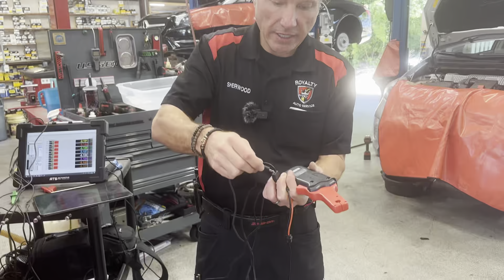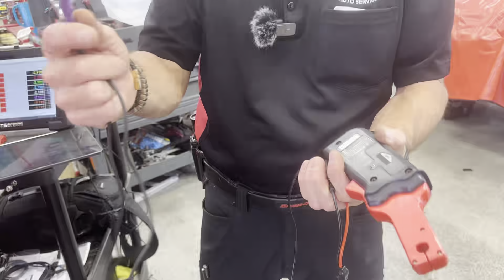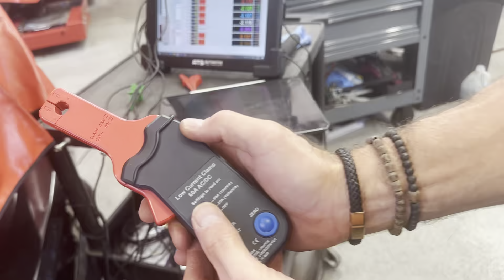amp clamp. So the amp clamp is going to come like that, okay? Go ahead and disconnect this, just how you did. These little black jumpers come in the kit, okay? You're going to take your lead, so I've got the purple lead. You're going to take the black jumper and close to the end, there's this little connection. You're going to take the ground side and go to that. And then you're going to take the lead and put it into the positive, and the little jumper wire you just hooked up into the negative. Turn it on to whatever amperage you want. Make sure you got a good battery.